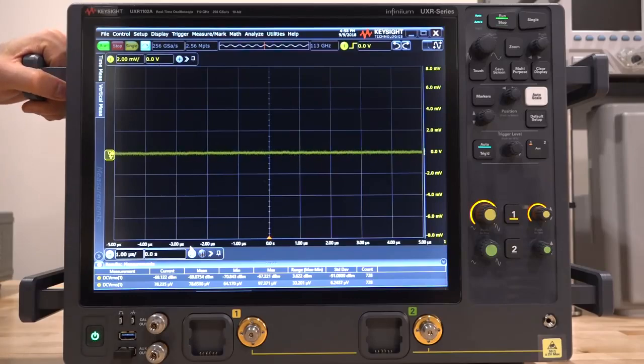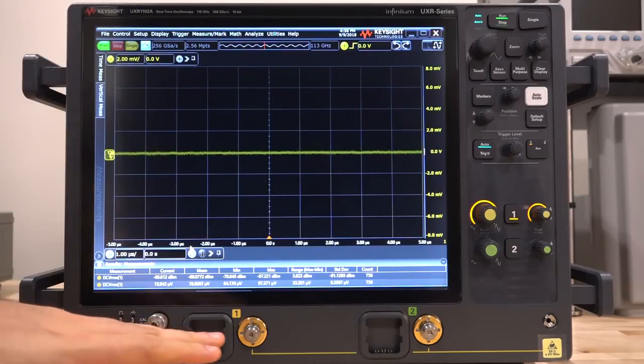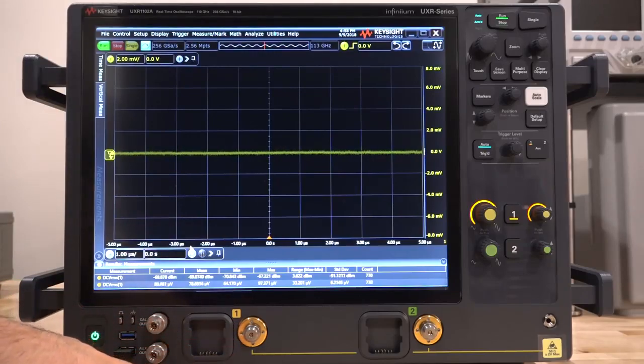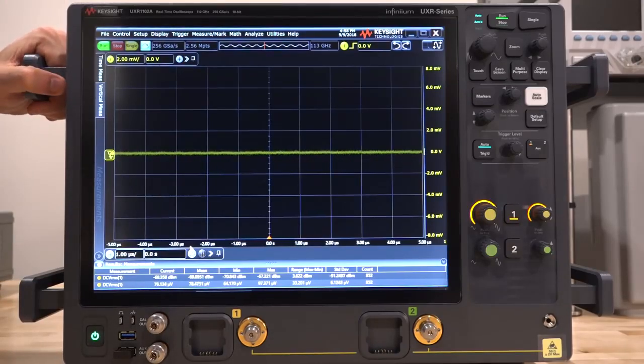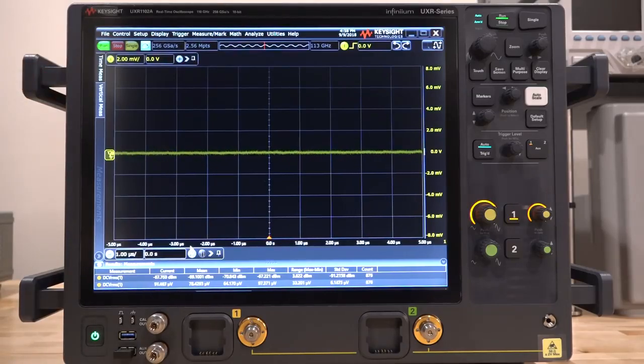That wouldn't be practical. So what they have done is create a probe that plugs in directly to the front, and that probe is their own design that creates a very sharp edge that allows you to calibrate the scope to the output of the probe. I'll show you that probe in just a second, and tell you how it works. It's a good, clever way of doing calibration directly in your lab, so you never have to send the unit back to get it NIST calibrated.